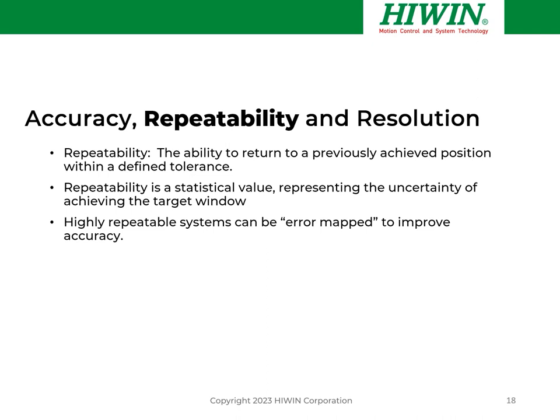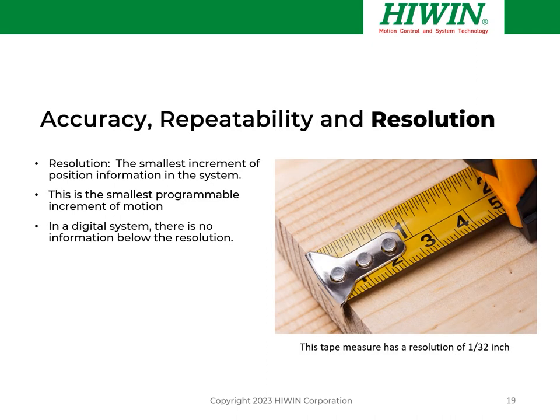Repeatability is the ability to return to a previously achieved position within a defined tolerance. It's a statistical value that represents the uncertainty of achieving a target window. Highly repeatable systems can be error-mapped to improve their accuracy through compensation or calibration. Resolution is the smallest increment of position information in the system — also the smallest programmable increment of motion in a servo system. But just because you can program it doesn't mean you'll achieve it. In a digital system, information is quantized — there's no information below the resolution. A common tape measure with 1/32-inch markings illustrates this: it has a certain resolution, but accuracy and resolution are not the same thing and one does not imply the other.